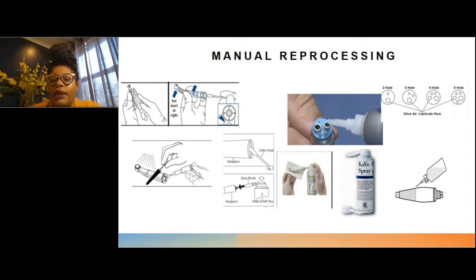So manual reprocessing, you'll see these excerpts or images are actually taken straight from IFUs of these handpieces. You'll see the description where there is a sponge being used to clean off the handpiece, a cotton swab to get into, not fully into the inner of the handpiece, but that's also a requirement. A wire brush, let's see, lubrication spray, lubrication oil. The IFU is indicating and pointing as to where these focal points need to be and all the areas that need to be addressed when reprocessing the particular handpiece.